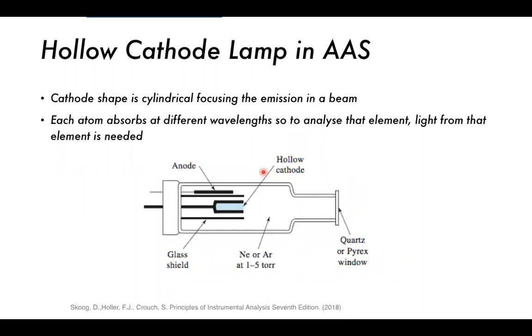The cathode shape is cylindrical so it can focus the emission into a beam. It looks like a U-shape or tuning fork in cross-section, but it is actually a cylinder. This cylinder causes the light to be focused out through a quartz or pyrex window, and that beam is directed towards the flame so that analyte atoms matching the cathode element can absorb it.